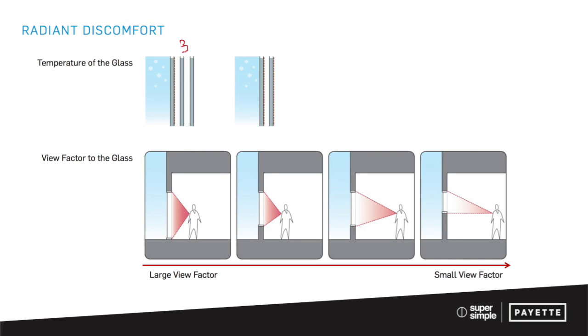For radiant comfort, there are two factors. One is the U-value of your glass — how much heat are you losing through it? If you have a really good triple-pane piece of glass, it's going to have a much warmer interior surface temperature, and you'll lose less heat to it because there's a lower delta T.